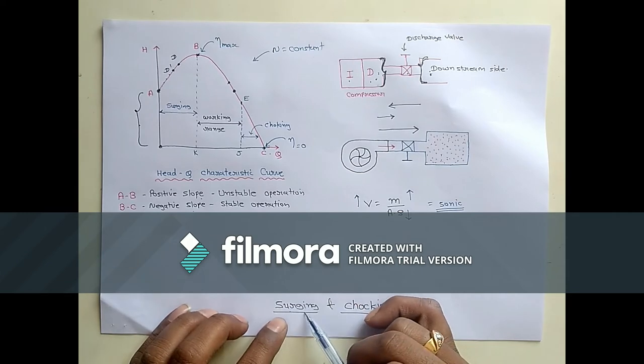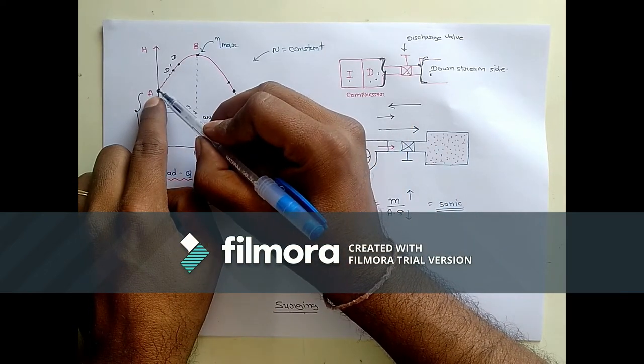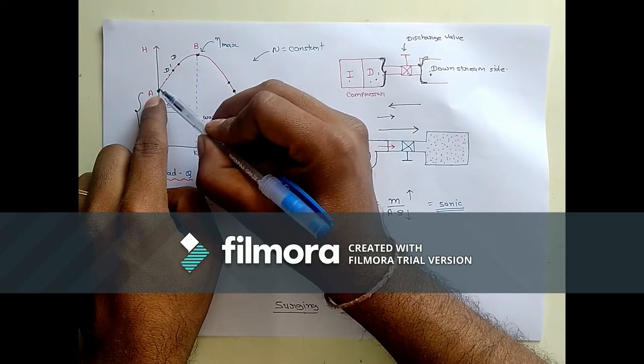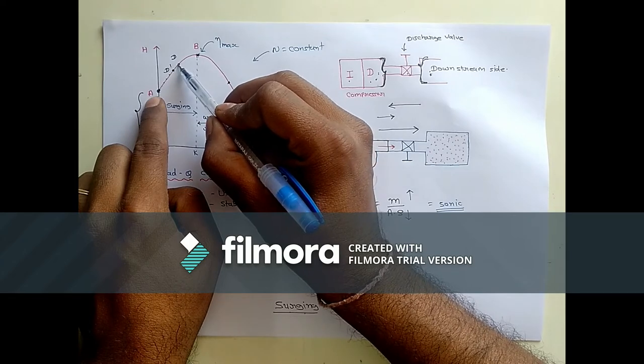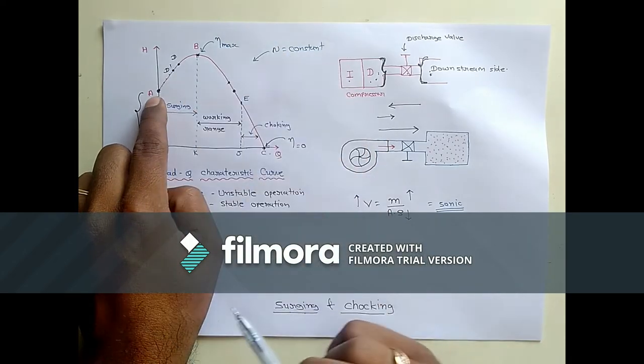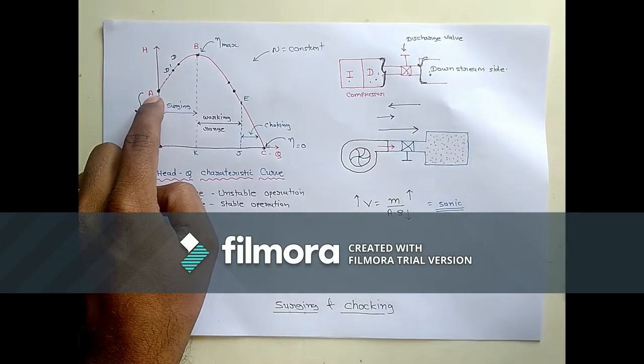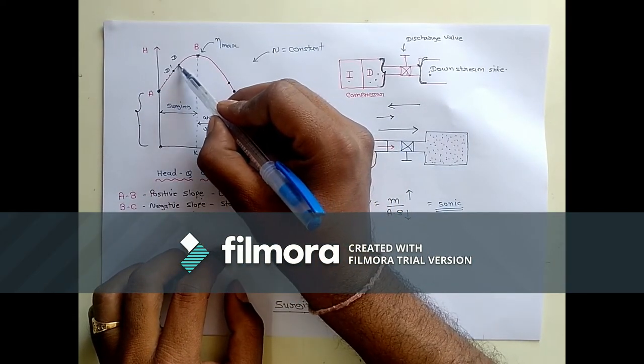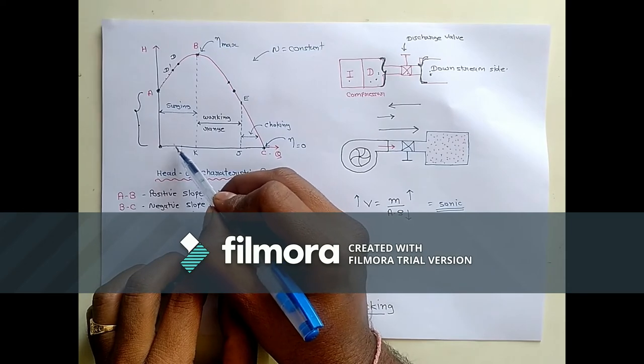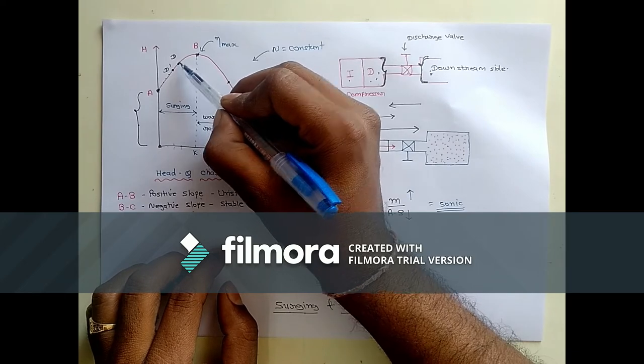Now we will talk about the surging process. What actually happens in the surging process — we look at the region from A to B, which is the positive slope region. At a particular point D in that region, due to increase in friction or increase in load, suppose the discharge gradually decreases from D to D dash. So discharge decreases, and since this point is on the positive slope side, its head also decreases.